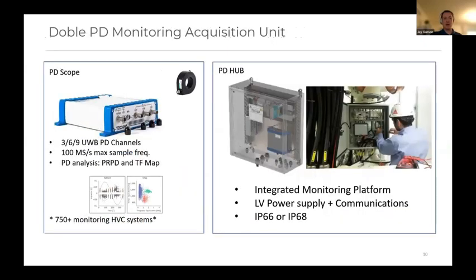The way we do that is by using a PD acquisition unit embedded inside an IP68 enclosure. That's really important because all of these vaults, as we all know, fill up with water. They can be dirty environments. So all of the system is IP68 rated. But effectively, we have the PD acquisition unit that connects to a sensor, a standard HFCT sensor, and takes up to 100 megasamples per second when we're doing an acquisition. And we take all of that data and we can process it using industry common and some proprietary functions to look at the PD activity on the cable, and we can do that in near real time.